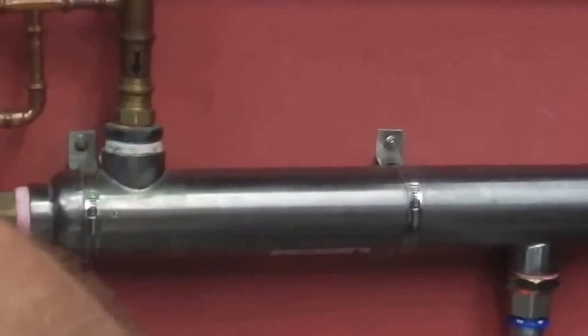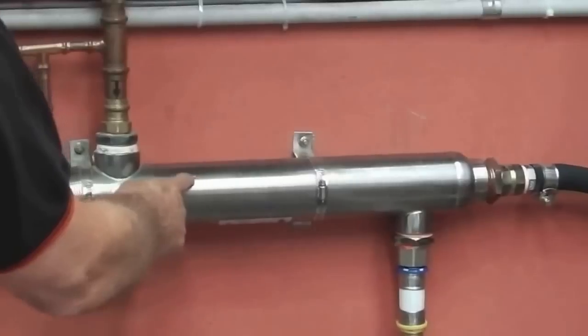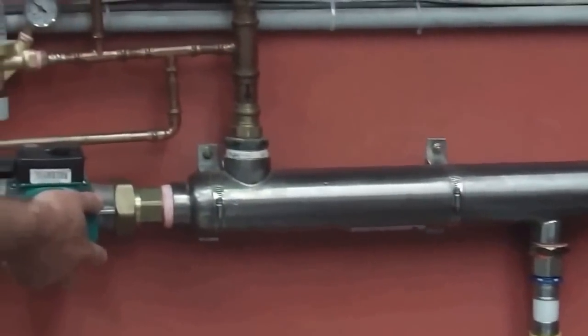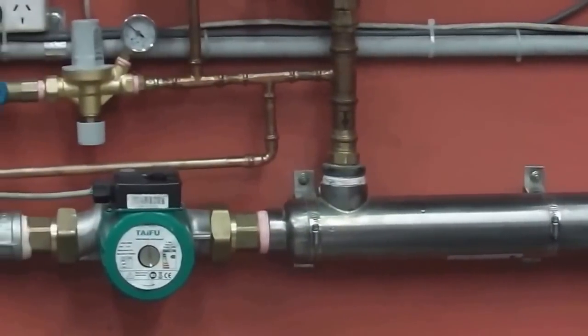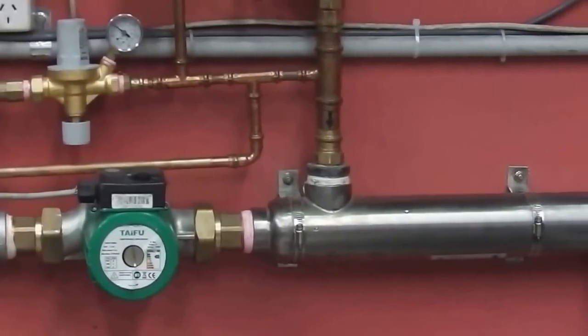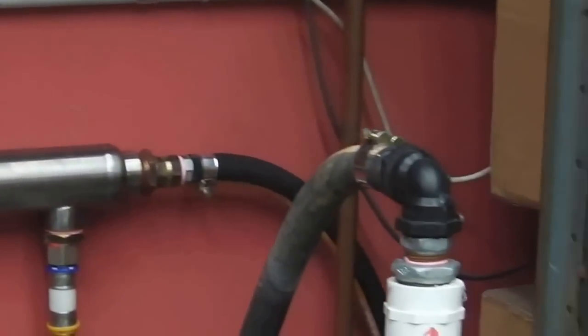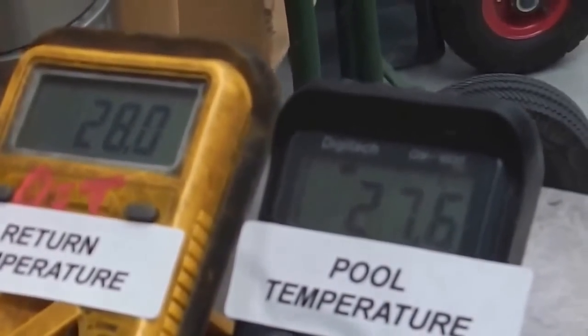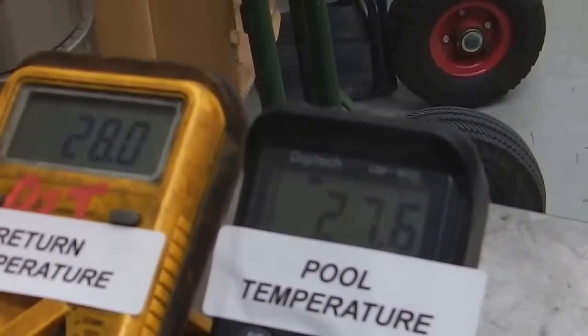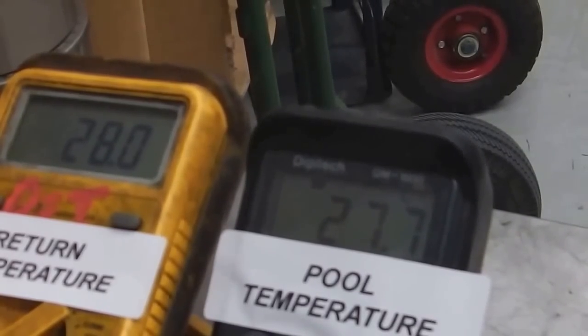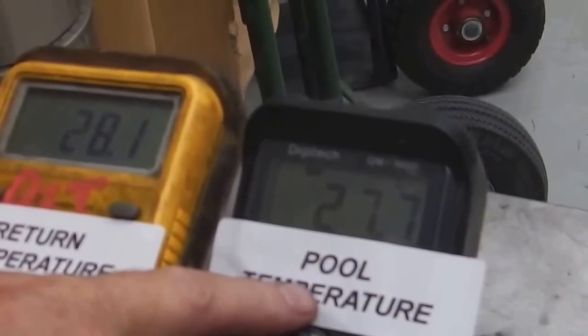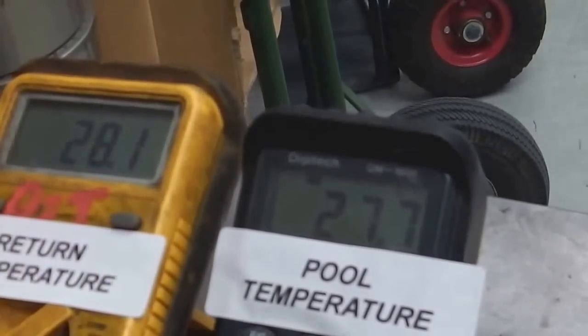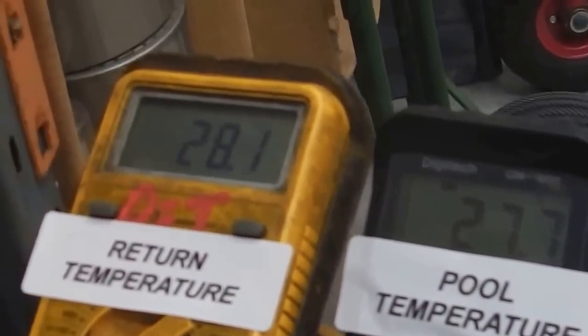Just going back to the heat exchanger over here, so the water from the boiler in fact comes through on this black 1-inch pipe through the middle of the heat exchanger. There's the circulating pump, comes out and back to our boiler. Okay. All right. So what we want to do is warm up our water in our swimming pool or our 44 gallon drum, and see how long it takes to lift the water temperature by 20 degrees centigrade. Okay. So our pool temperature's over here. It's sitting at about 27.7, and our return temperature side.